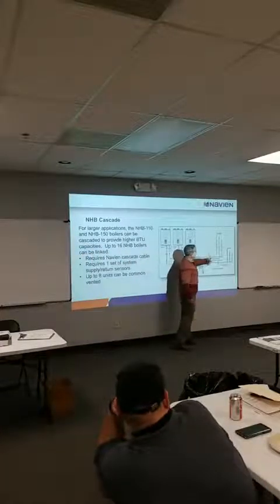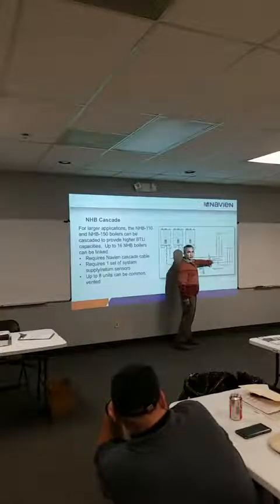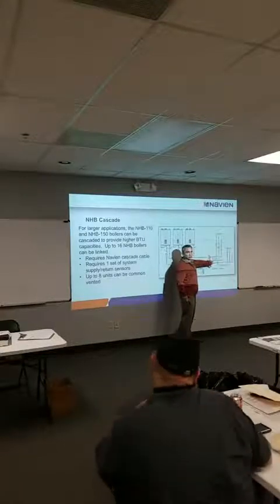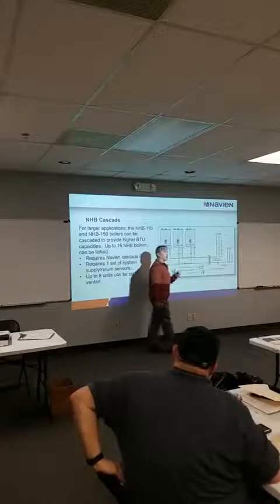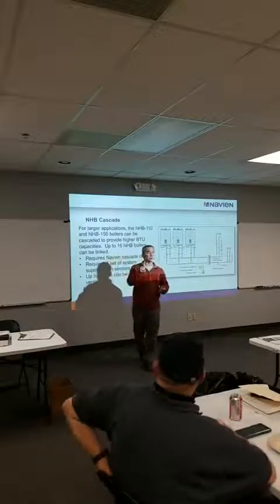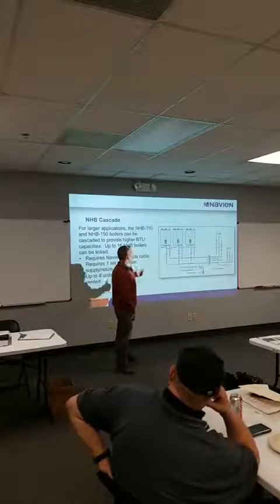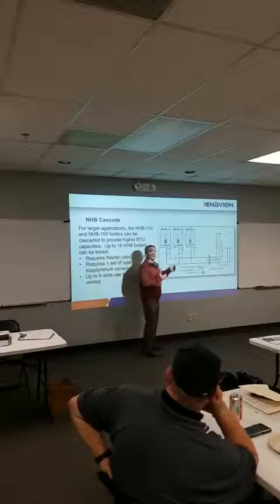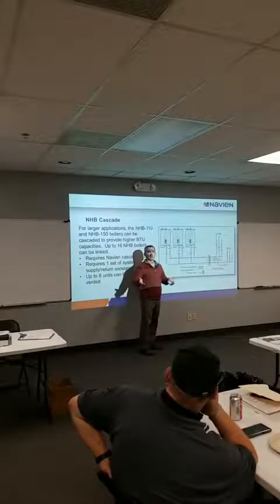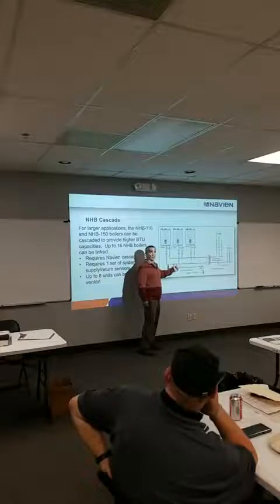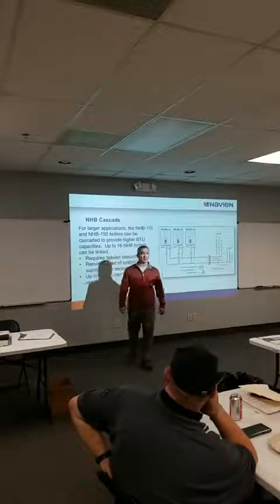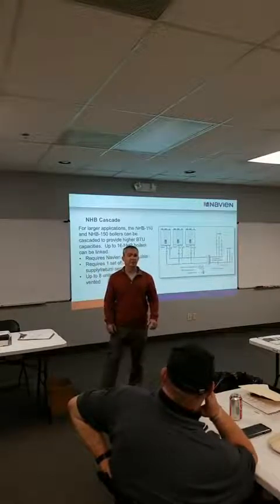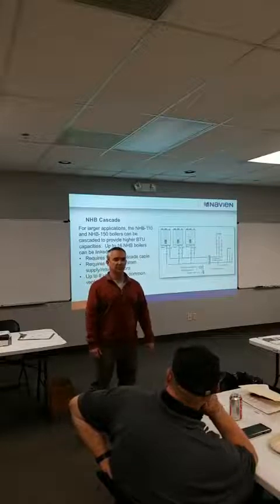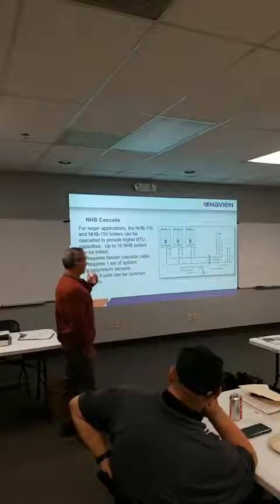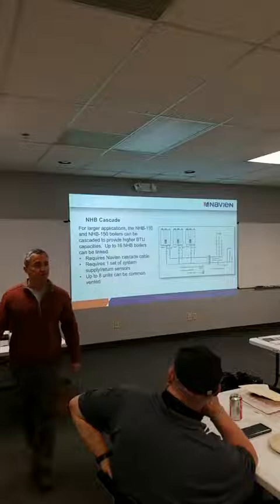The NHB does not come with these. You have to buy the return supply sensors. I think they're like $20. All the other boiler equipment gives you 1 sensor in the box. So if you're doing multiple boilers, you're gonna have extra sensors with you, so you don't have to buy any other sensors. And I think they're gonna make that change in the NHP when they come out with the new version. Those are all strap-on too, right? Yes, it's just a basic strap-on temperature sensor probe that wires back to the low voltage side of the board.